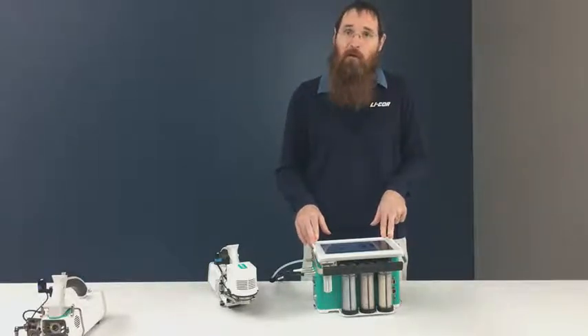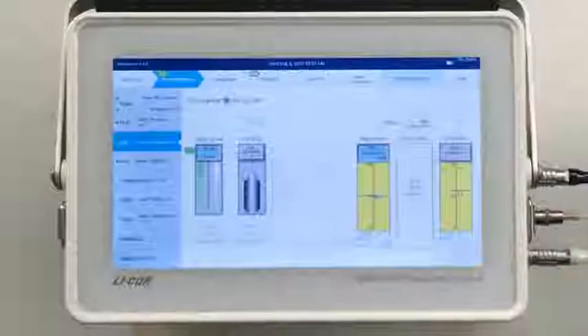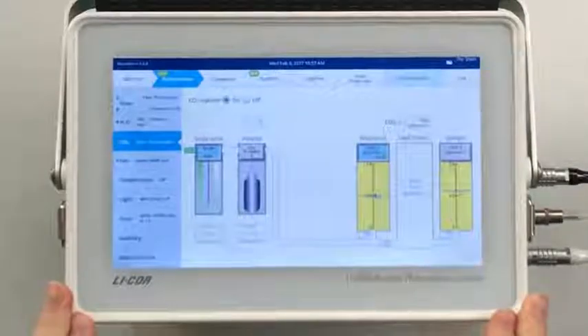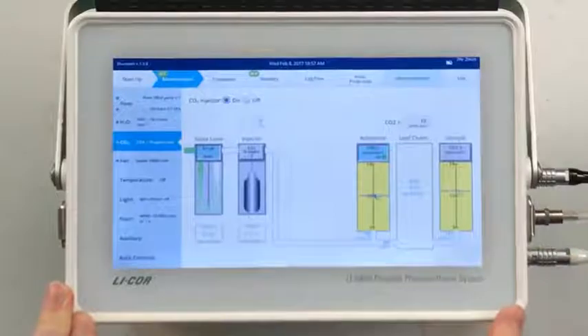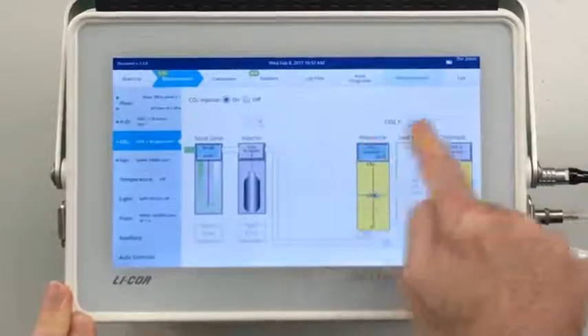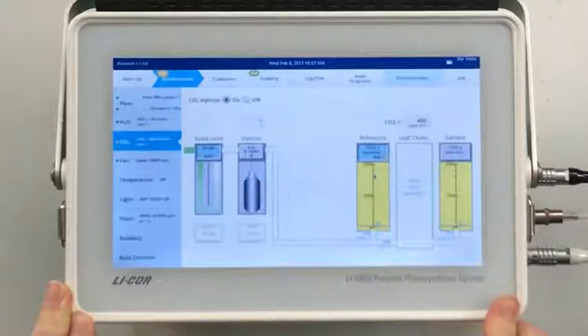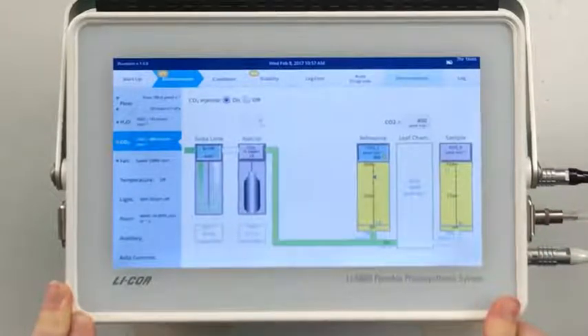In the 6800, if I want to do high resolution measurements at the low end of an ACi curve, I have the control capacity to do this, right? And if I want to set it to something different, something reflective of ambient, I can type in that value, and fairly quickly the instrument should go there.